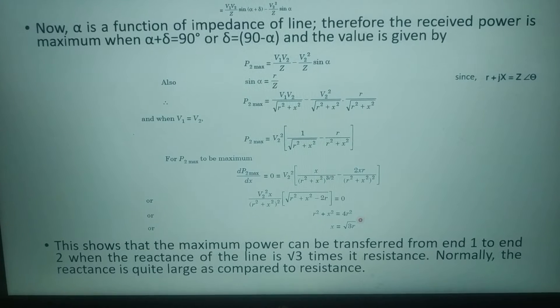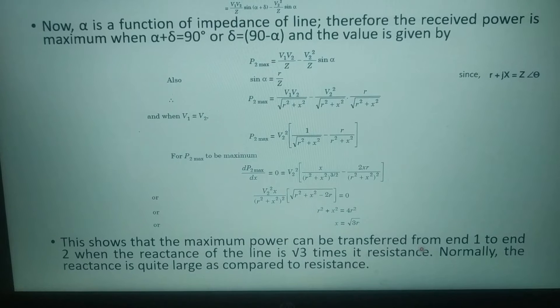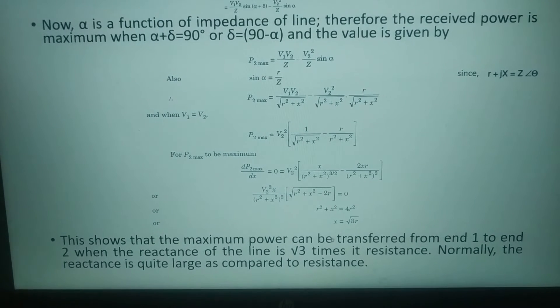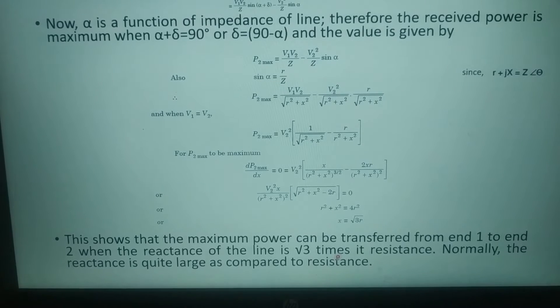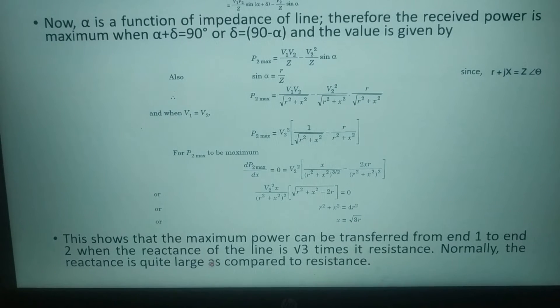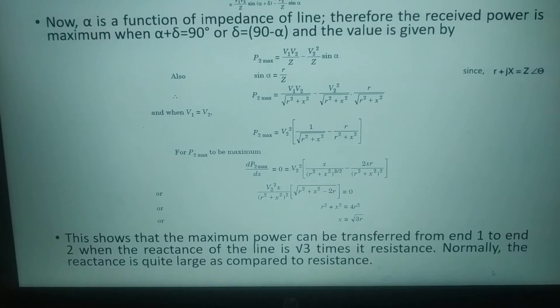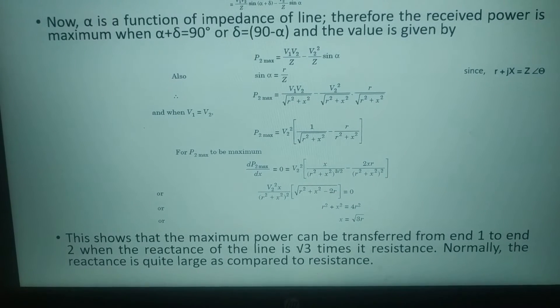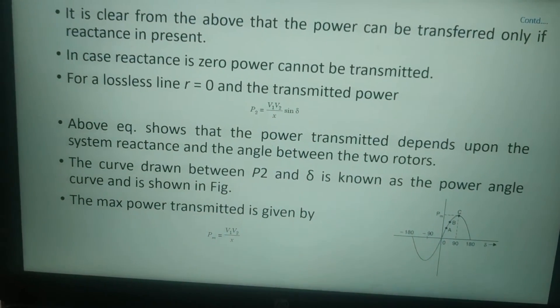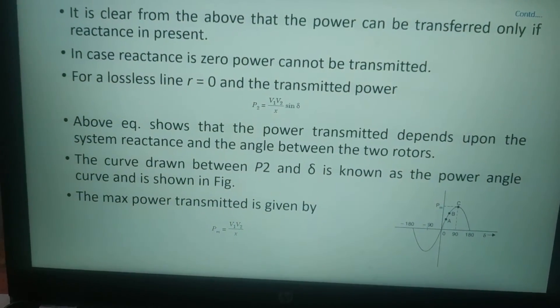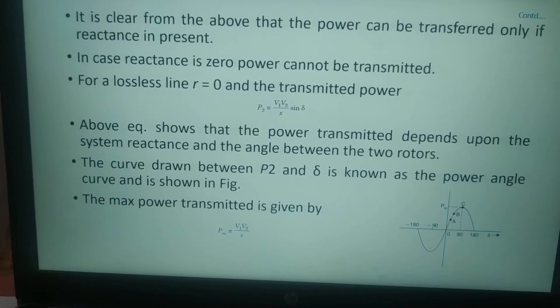Further simplifying, we get X equals sqrt(3)*R. So the maximum power can be transferred from sending end to receiving end when the reactance of the line is root 3 times its resistance. Normally the reactance is quite large compared to the resistance. It is clear that power can be transferred from sending end to receiving end only if reactance is present in the line.